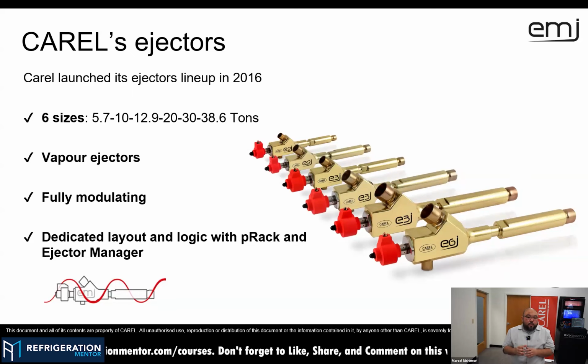And another difference on our ejector is that it's a modulating ejector. So we have an internal motor inside the ejector, and with this motor, we can modulate the refrigerant flow inside it. And with that, we can reach the precise need for the system. So let's say the first feature or the first requirement of the ejector is to work as an HPV valve, so a high pressure valve.